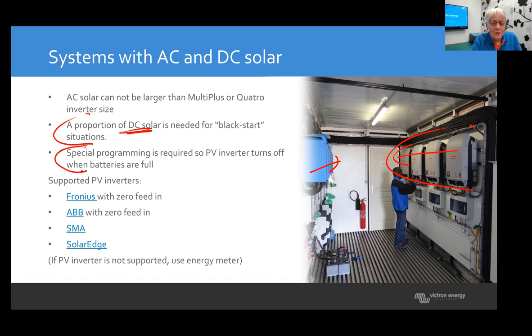And be aware that you always need special programming. You need to tell the inverters what to do, especially in situations where the batteries are full. As soon as the batteries are full, we need to turn the inverters off, and we do that with a frequency shift. I've explained that in my previous webinars as well. If you don't program the frequency shift in, you will eventually overcharge your batteries and damage them, and you can potentially damage other DC equipment. It can go really wrong. So these are the 3 rules: not larger, consider DC, we almost recommend DC, I would almost say, and special programming. So be aware that if you add AC, you will always have to do these 3 steps.